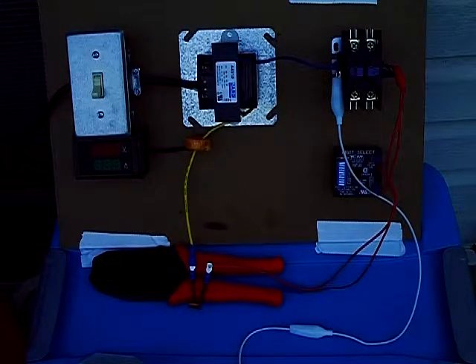And have you ever thought why, if these 40 VA transformers that the fuse protects are only meant to handle about 1.6 amps, they have a 3 or 5 amp fuse in that circuit board? Well, it's because it's protecting from electrical storms and those inrushes. It'll draw past that 1.6 amps, and you don't want to keep going out to a house after every storm to replace a fuse, so they oversize it a little bit.